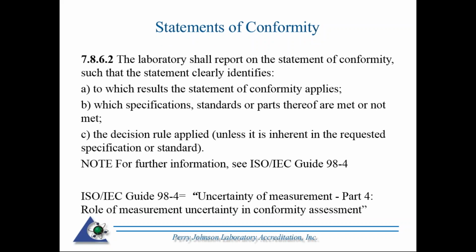7.8.6.2. The laboratory shall report on the statement of conformity such that the statement clearly identifies to which results the statement of conformity applies, which specifications, standards, or parts thereof are met or not met, and the decision rule applied, unless it is inherent in the requested specification or standard. And here's a note for further information, ISO Guide 98-4. And I looked that up. That is actually the Uncertainty of measurement, Part 4: Role of measurement uncertainty in conformity assessment.